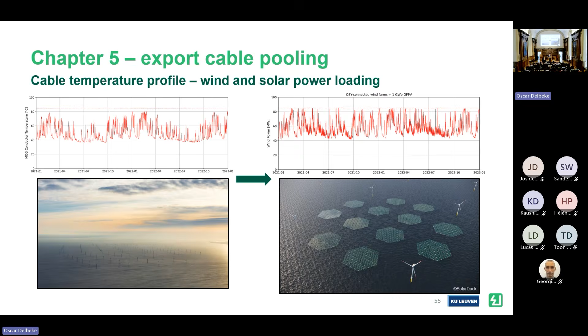But you saw also that sometimes I get very close to the 90-degree limit. And at a certain point, if I would just send all solar and wind power through these cables, they would overheat. So I make the decision to curtail power. Power curtailment is a bit like turning down the tap so that your sink does not overflow.